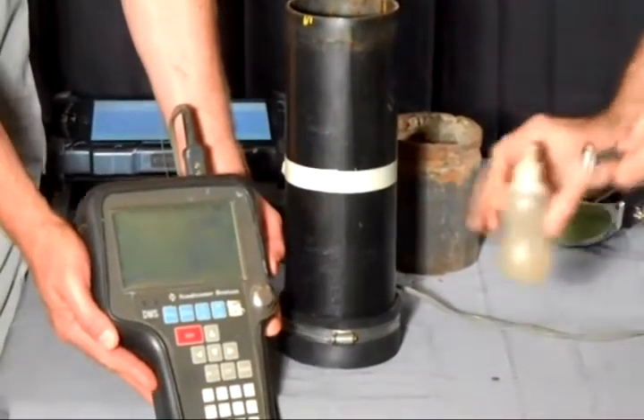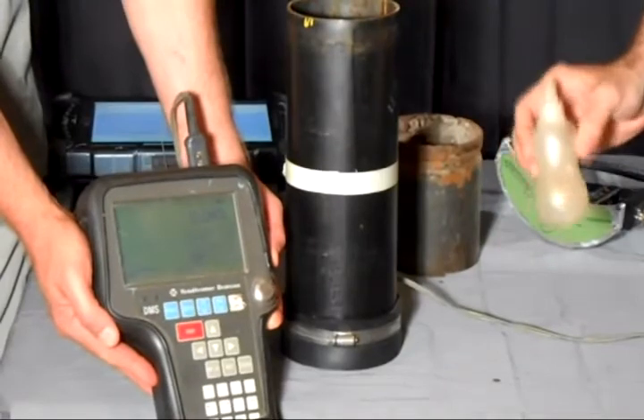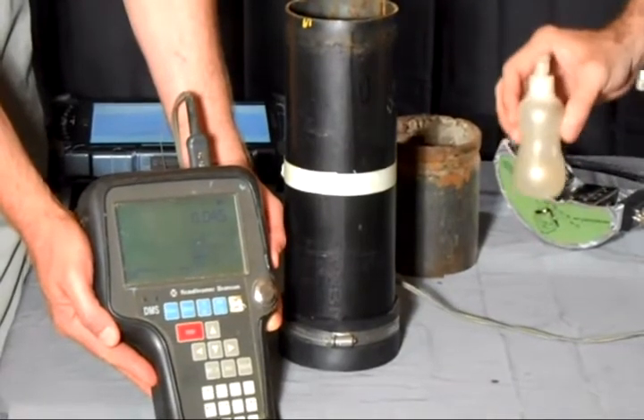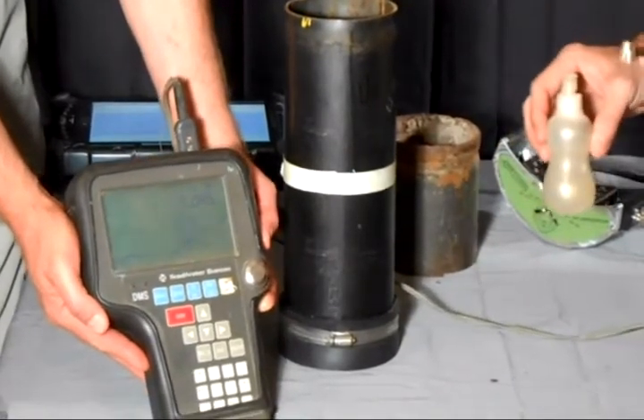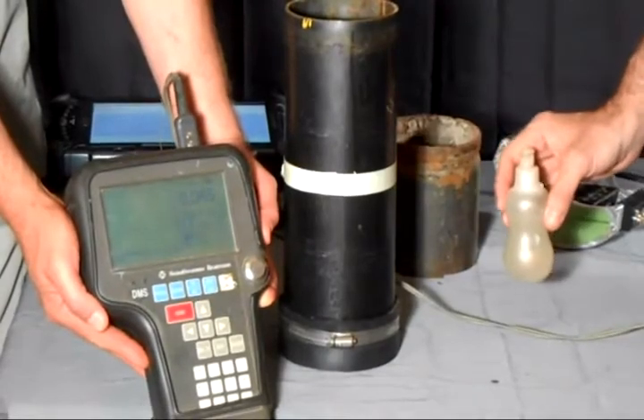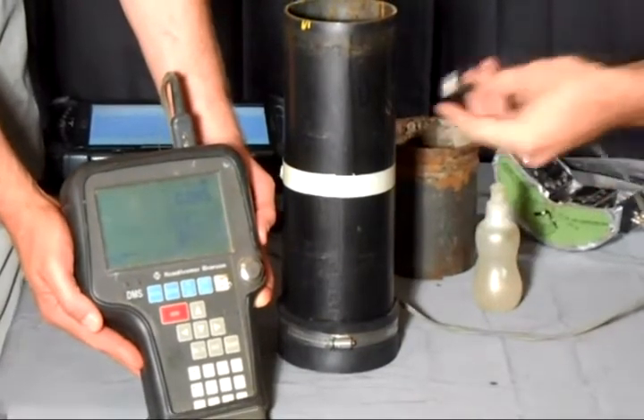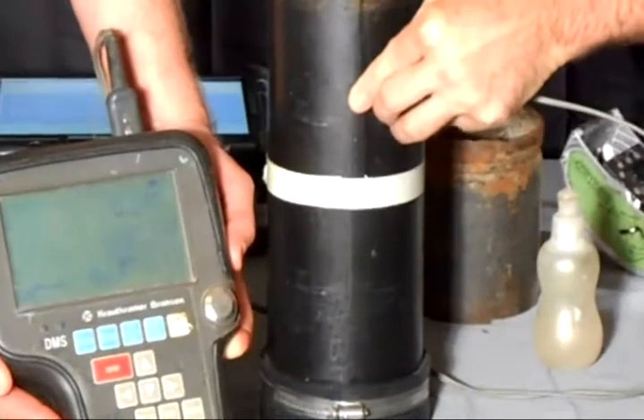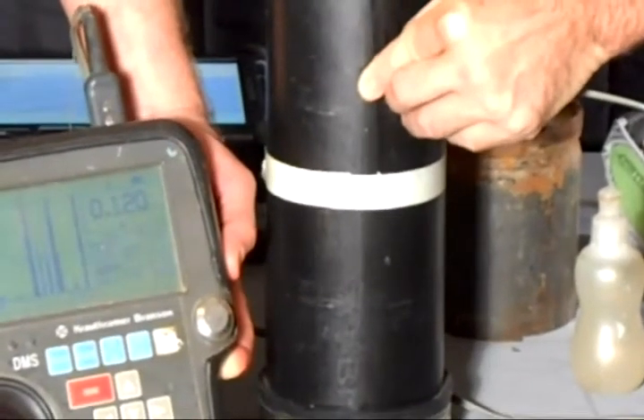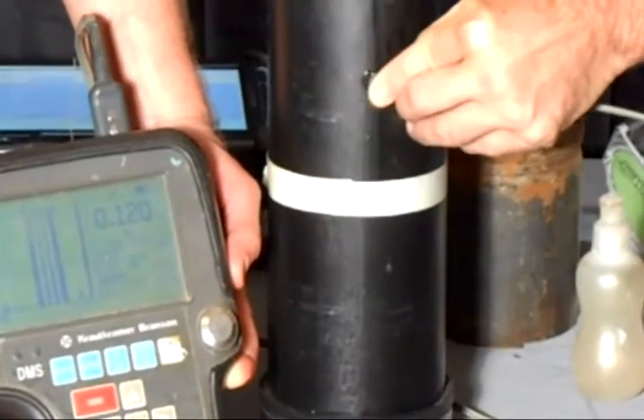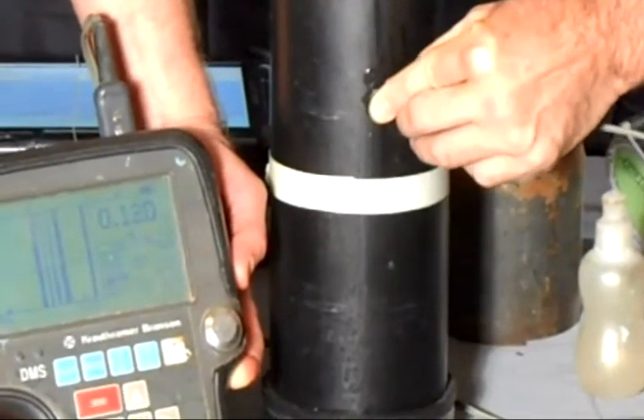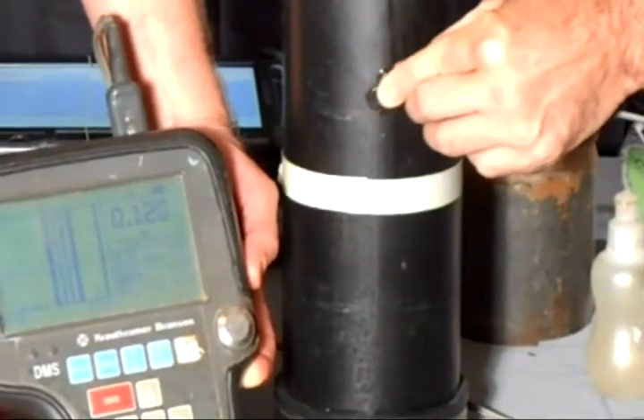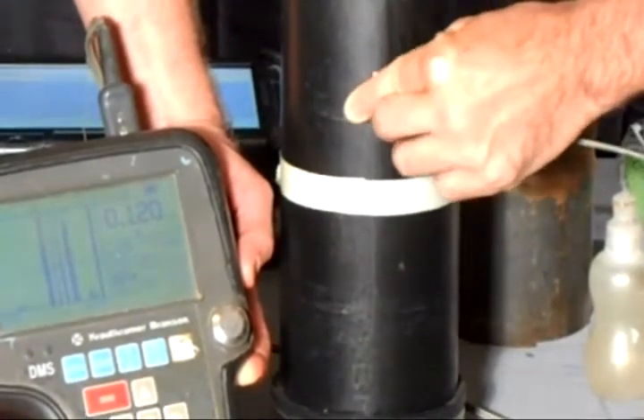Putting a little bit of couplant on the probe. Couplant kind of acts like the same jelly they use for a woman's ultrasound. It helps create a good seal between the transducer and the material that we're measuring. And what I'm going to do is just hold this up against the pipe. You can see here that this is measuring at 120 thousandths, which is exactly at nominal for this size pipe. I move around a little bit, 120, 121.